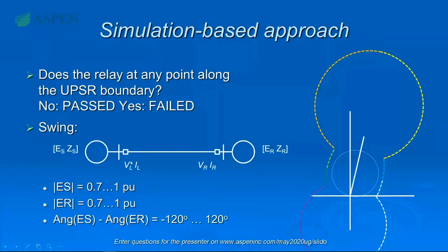We take this as a reference number — call it value A. Then we simulate faults along the transmission line, and for each fault simulation we take the simulated three-phase voltage and current values at the relay group as input to these algorithms, generating another percentage — value B. The fault location is found when the minimum difference between value A and value B is found. We also adjust the fault resistance to minimize this difference. When we click OK to run the fault locator, the modified Takagi algorithm cannot be used for three-line-to-ground faults and line-to-line faults, so for line-to-line we need to uncheck that checkbox.